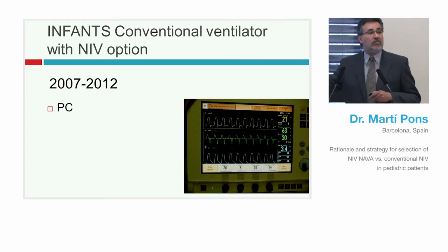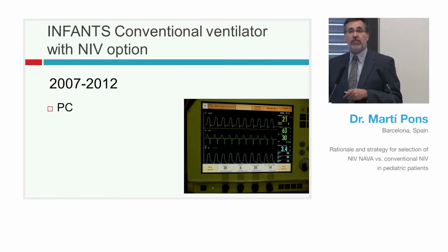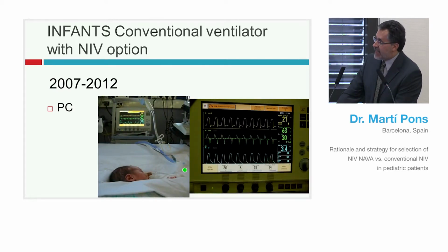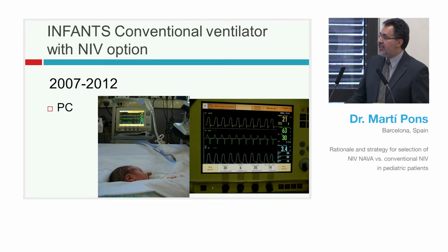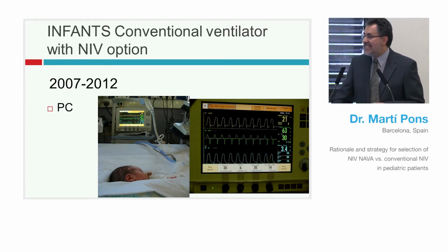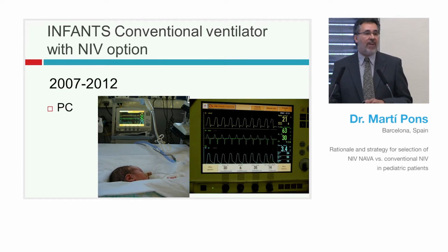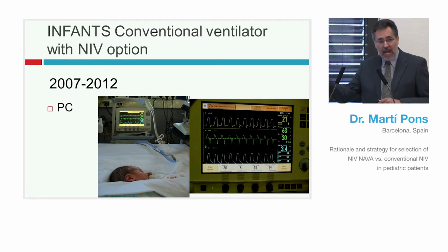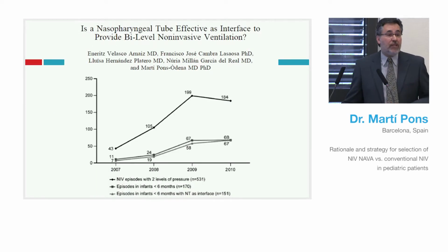We can see here on the screen, perhaps it will be very difficult, we can close the lights for a short while in order to see the screen. Could that be possible? Well, no. We can see here that the patient is connected to the ventilator through a nasopharyngeal endotracheal tube that is inserted 7 centimeters into the nostril. Why did we decide to insert it 7 centimeters? To be as close as possible to the glottis and to capture the inspiratory effort of the patient. Wow, I have to say that it works.